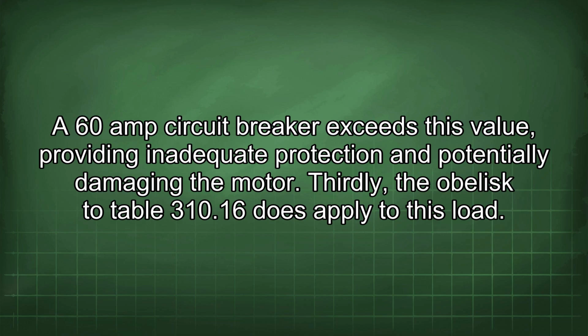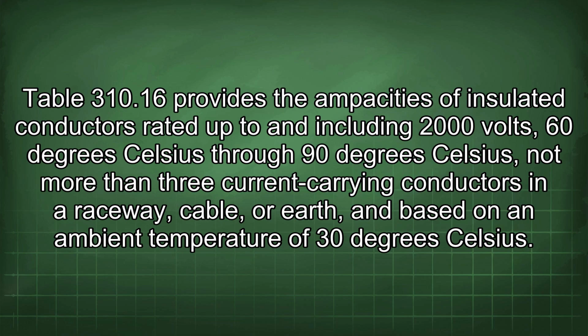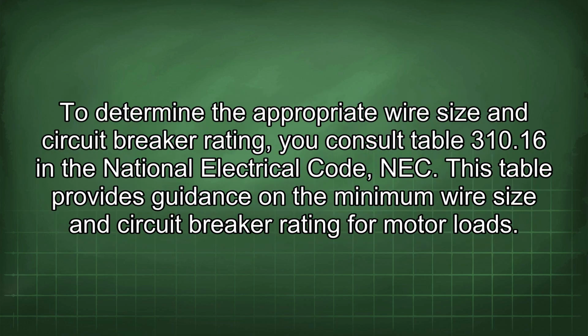Thirdly, Table 310.16 does apply to this load. Table 310.16 provides the ampacities of insulated conductors rated up to and including 2000 volts, 60 degrees Celsius through 90 degrees Celsius, not more than 3 current carrying conductors in a raceway, cable, or earth, and based on an ambient temperature of 30 degrees Celsius. To determine the appropriate wire size and circuit breaker rating, you consult Table 310.16 in the National Electrical Code, NEC. This table provides guidance on the minimum wire size and circuit breaker rating for motor loads.